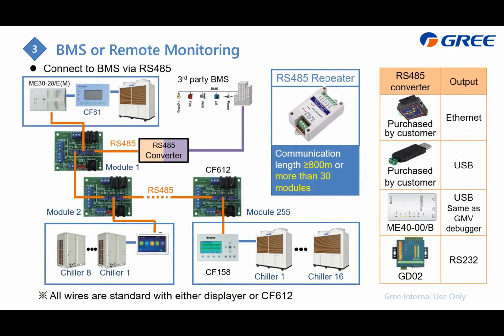If you would like to control different series, which are the on-off and the inverter, by the PC or the BMS system, you need this CF612 to combine them together. From here the output is already RS485, so you just need to combine them together and allocate different addresses. In this case there are 3 systems combined, output from here, then through this RS485 converter, then to the PC.